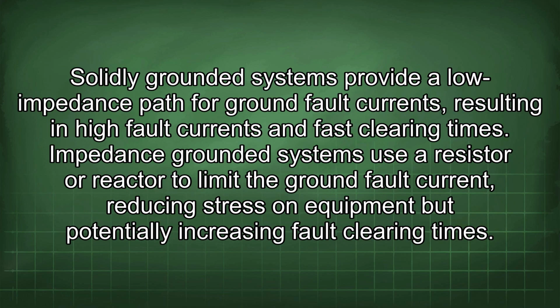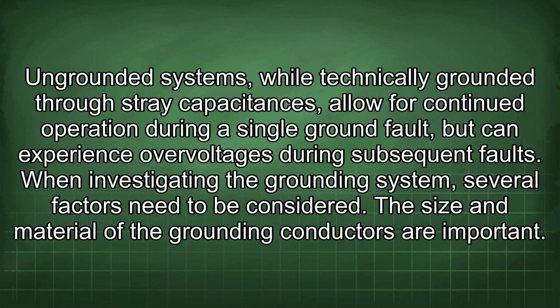Solidly grounded systems provide a low impedance path for ground fault currents, resulting in high fault currents and fast clearing times. Impedance grounded systems use a resistor or reactor to limit the ground fault current, reducing stress on equipment but potentially increasing fault clearing times. Ungrounded systems, while technically grounded through stray capacitances, allow for continued operation during a single ground fault, but can experience overvoltages during subsequent faults. When investigating the grounding system, several factors need to be considered.